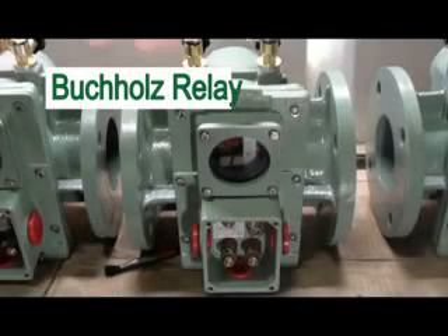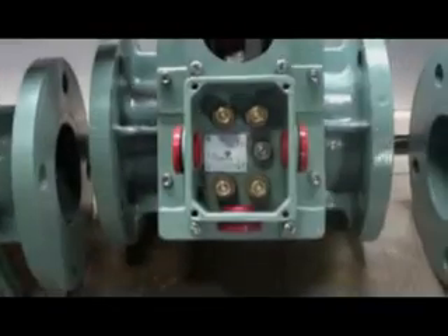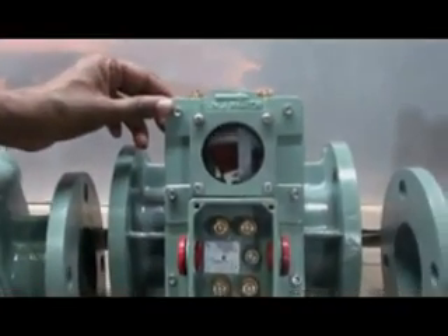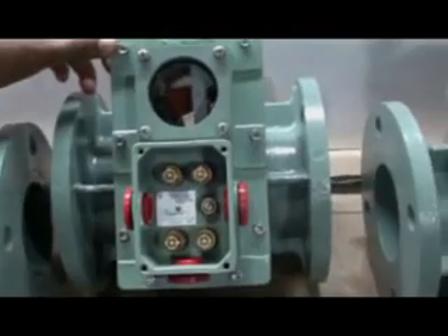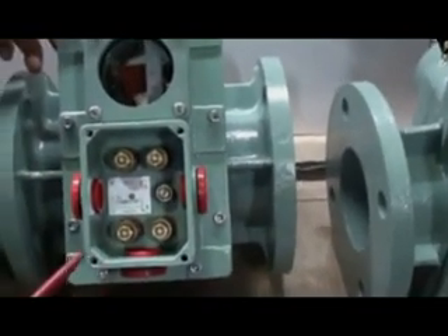This is a Buchholz relay. Presently I am removing the terminal cover. Now in the terminal box, the upper side has terminals for alarm circuit connection and the bottom has terminals for trip circuit connection.